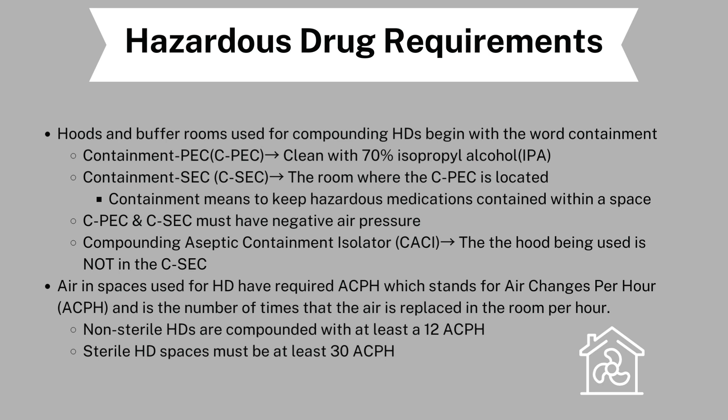Both the CPEC and CSEC require negative air pressure. We also need a compounding aseptic containment isolator, which is another type of hood different from the one used in the CSEC. Air in spaces used for hazardous drugs requires a specific ACPH — air changes per hour — which is the number of times the air is replaced in the room per hour. Non-sterile hazardous drugs need at least an ACPH of 12, while sterile hazardous drugs need spaces with an ACPH of at least 30 or higher.